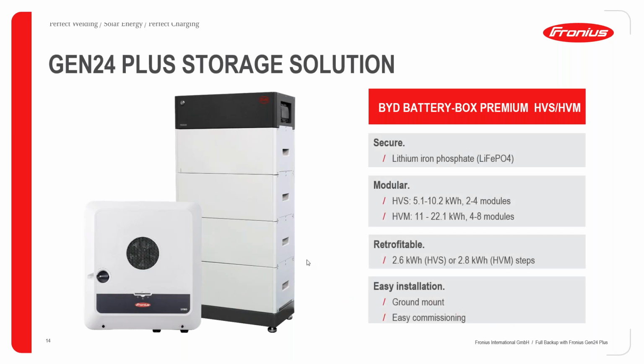Okay, just having a very basic look at the battery. This is how the battery looks, the BYD Premium HVS HVM. It's lithium iron phosphate technology. It comes with a very modular structure, so it starts from 5.1 kilowatt hours up to 10.2 kilowatt hours per tower. Okay, and per tower with the HVS, you need 2 to 4 modules. So the minimum amount of modules you need with the HVS is 2, and the maximum is 4 modules per tower. If you look at this tower over here, each light gray block is about 2.56 kilowatt hours. And then the black box on the top is basically the BMS system. So what's important to note is that each BYD Premium tower needs a BMS system.